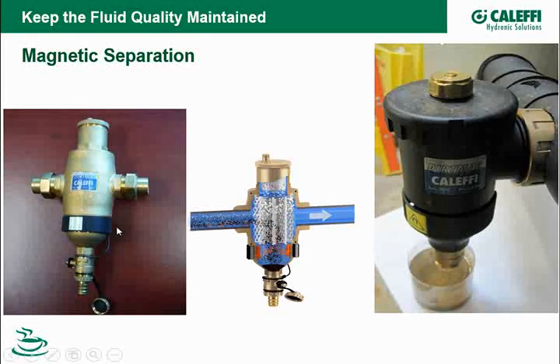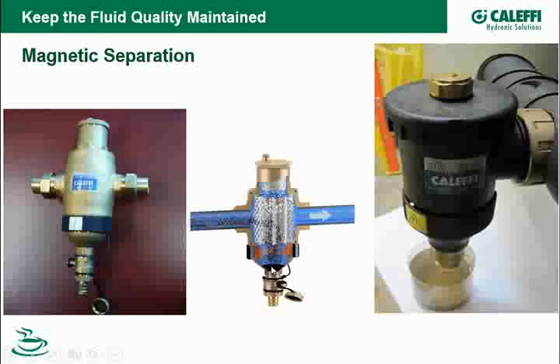And here's a couple examples of the products that we offer from Caleffi. This is what we call our combination air and dirt with a magnetic band on it. Basically what you do is you come back to this job, and I like to put a cup or a white 5-gallon bucket under here and just open this valve here and just blow down. You got to take the magnet off, give it a second or two for the particles to settle to the bottom of the cup here, like you see in the middle picture, and then you can just blast it out the bottom here.